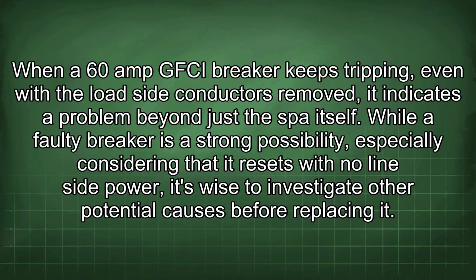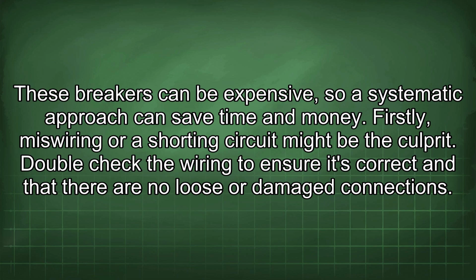When a 60 amp GFCI breaker keeps tripping, even with the load side conductors removed, it indicates a problem beyond just the spa itself. While a faulty breaker is a strong possibility, especially considering that it resets with no line side power, it's wise to investigate other potential causes before replacing it. These breakers can be expensive, so a systematic approach can save time and money.